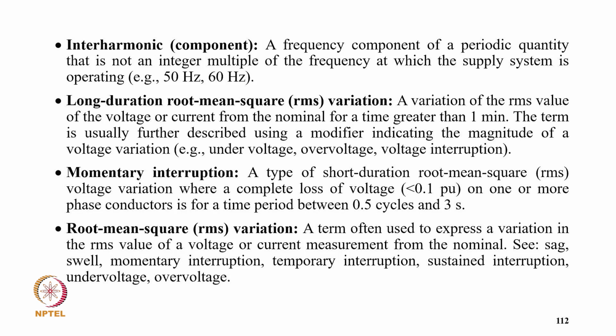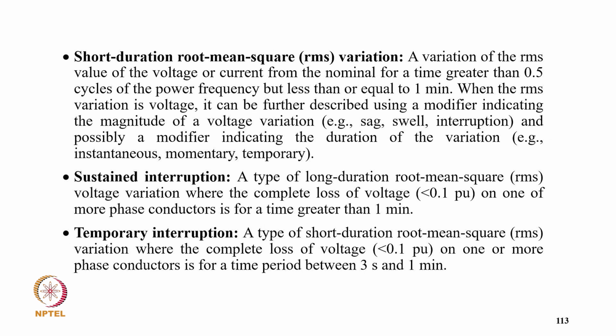The term is usually further described using a modifier indicating the magnitude of voltage variation: undervoltage, overvoltage, and so on. Momentary interruption: a type of short duration RMS voltage variation where the complete loss of voltage, less than 0.1 per unit, on one or more phase conductors is for a period of 0.5 cycle to 3 seconds. Root mean square variation is a term often used to express the variation in RMS value of voltage or current from nominal. See also momentary interruption, temporary interruption, sustained interruption, undervoltage and overvoltage.